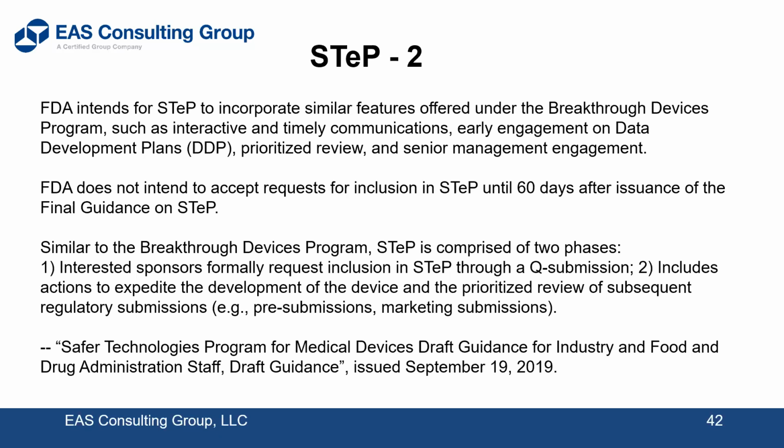Notice here in the middle paragraph, they're similar to the Breakthrough Devices Program. STEP is comprised of two phases. Interested sponsors formally request inclusion in the STEP through a Q-Submission, and then it includes the actions to expedite the development of the device and prioritize review of subsequent regulatory submissions, pre-submissions, marketing submissions. You may be put a little bit at the front of the line, so to speak, but also during the process, you'll be expedited during the review process itself. Now, I haven't seen any breakdowns of what has actually transpired as they've implemented these programs. I'm sure they're tracking it, but I haven't seen that.